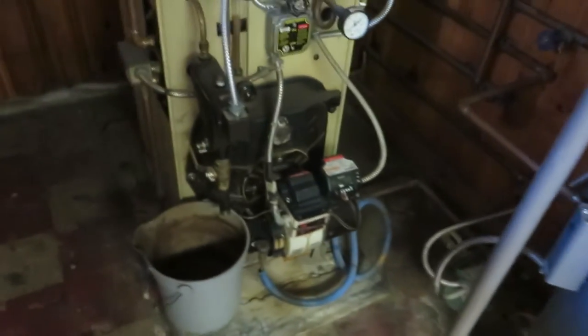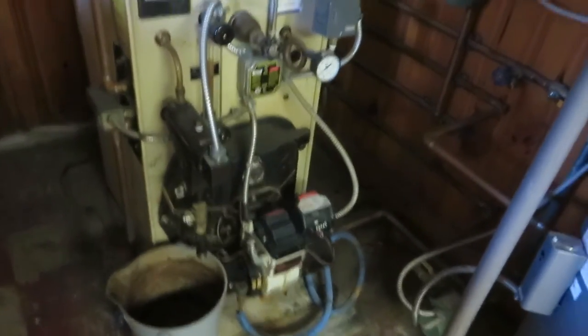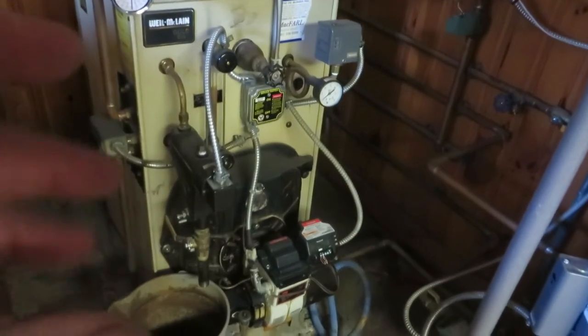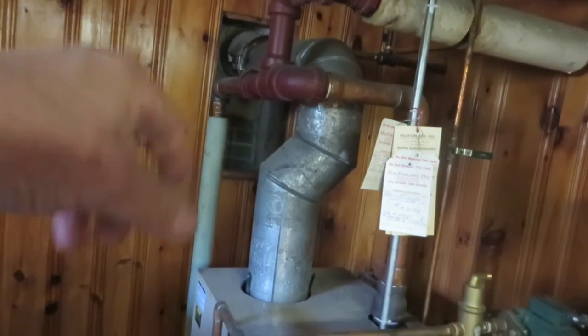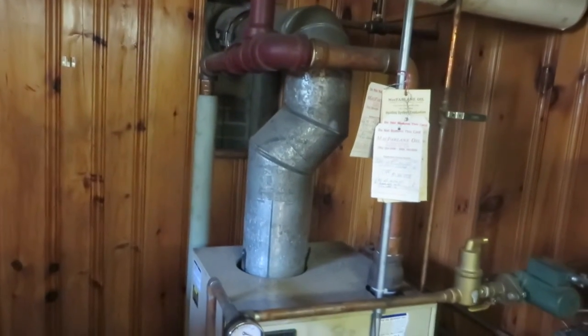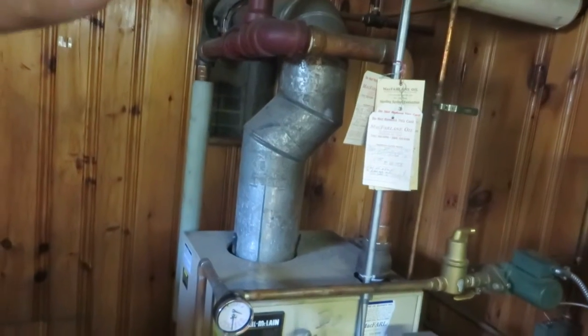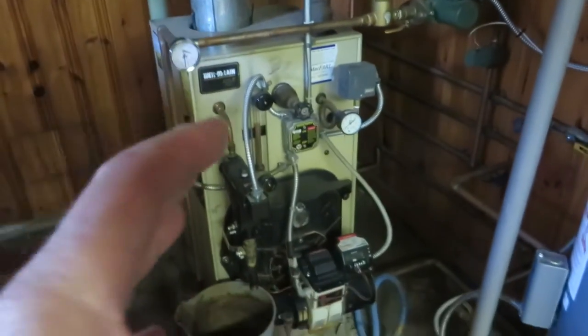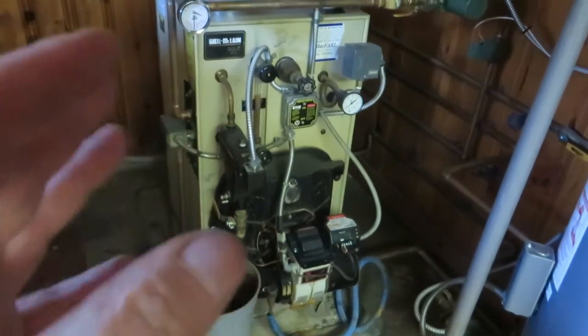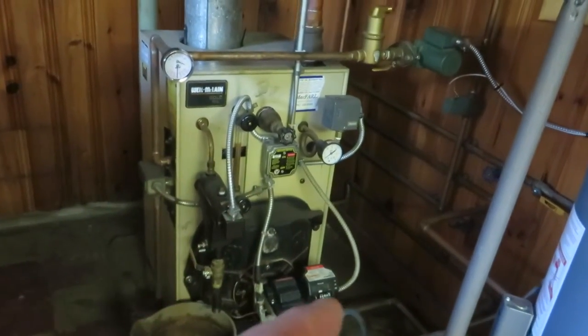We've got a Weil-McLain Gold Cast Iron Sectional Oil Fired Boiler. We've got a metal liner in the chimney — we'll see that when we look at the ash dump picture I took. They lined it, which is appropriate. So we've got steam heat in the original house, and then we have forced hot water and electric in the additions.